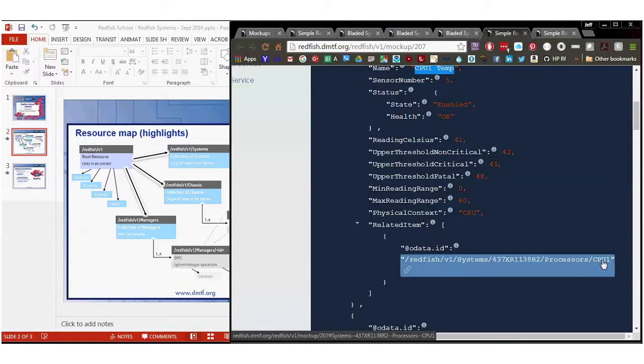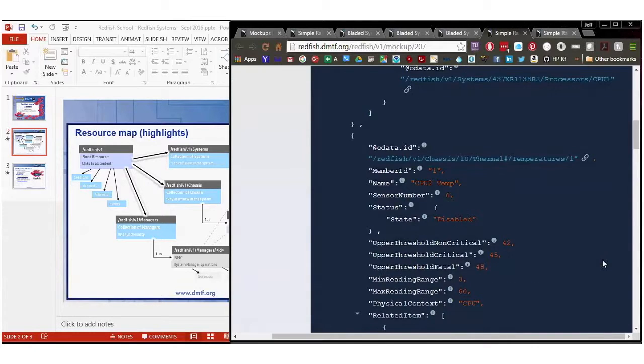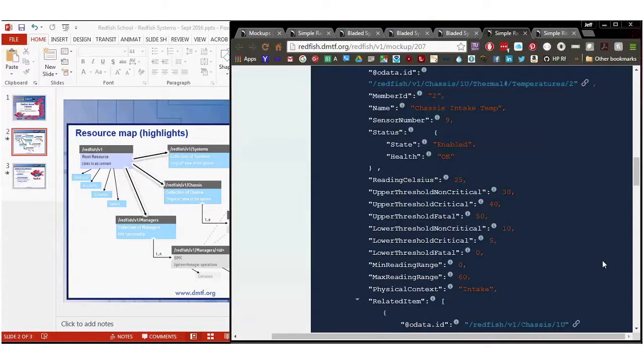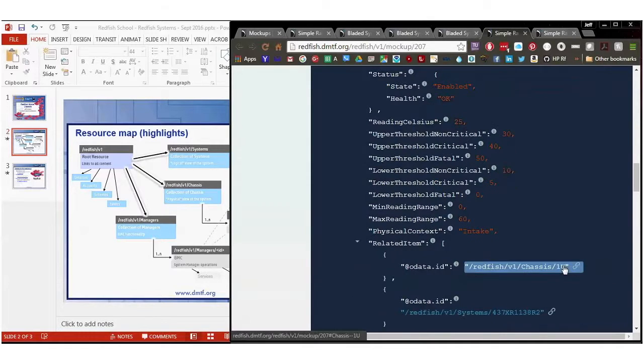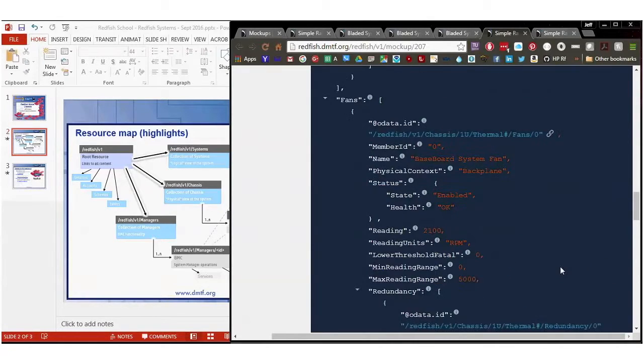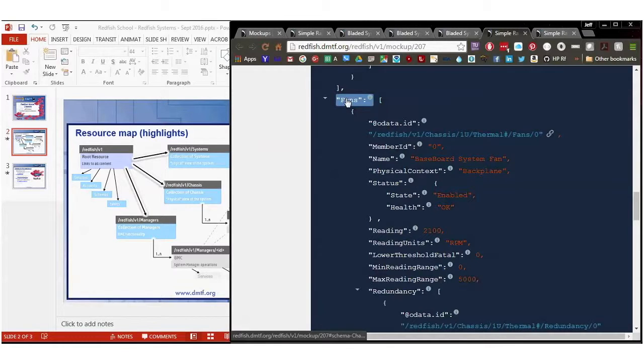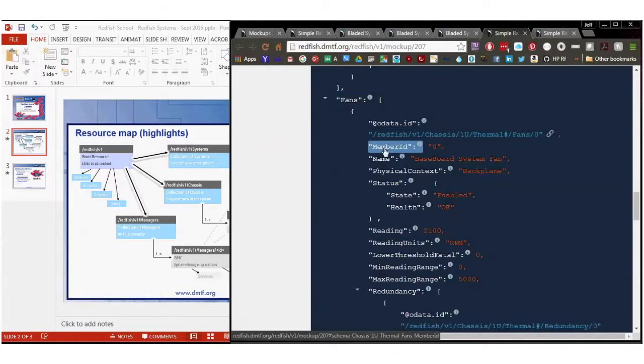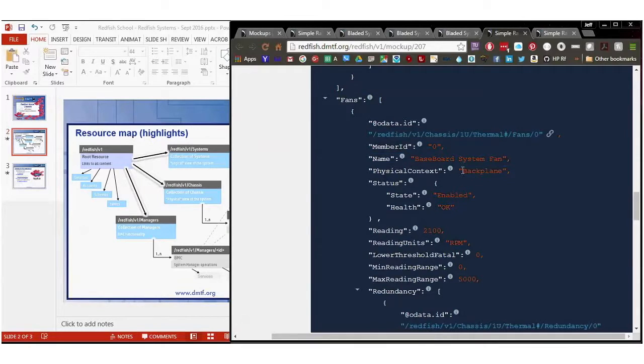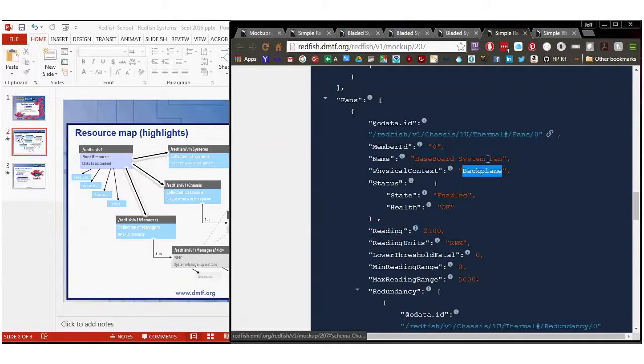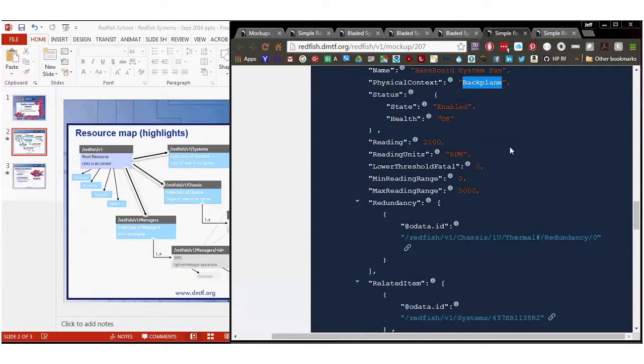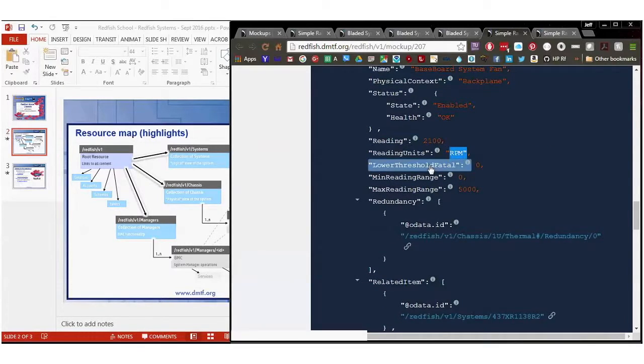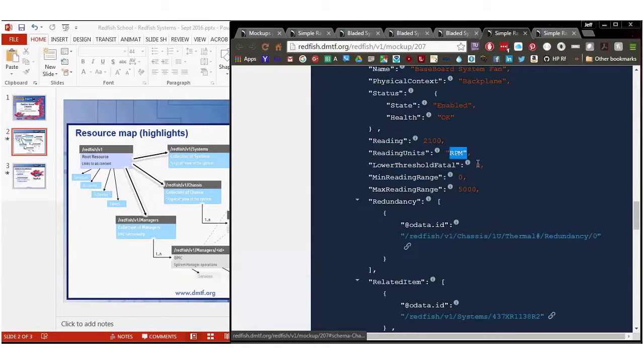There's more temperature sensors in here. There's one for CPU two, and there's one for the chassis, and I'm going to ignore them right now because there's another array that's important, and that one's called fans. And here it's just like the temperatures array, only slightly different. It's got a name, physical context. This one is a backplane, but a program could never figure out that it's actually the backplane fan, and that's why we have the related item in there. So this is fan zero. It's got its current reading. Its reading in units is RPM. Lower threshold is zero. Max range is 5000. So at 2100, it's running about medium.